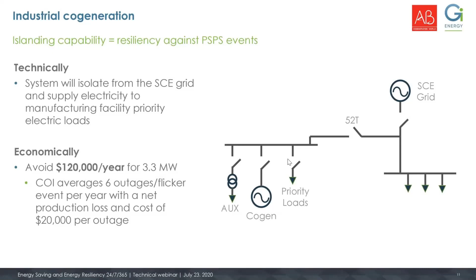Why do we go through this together with the customer? Because the ability to avoid outages can be worth a lot of money for our customers. Cogen units were originally driven by energy savings, but today the value of an outage can be quite substantial at a facility. In the example from the previous slide, savings from efficiency and low cost generation were approximately $500,000 per year, and the resiliency benefit added up to $120,000 more - quite substantial and relevant for a cogeneration business plan.